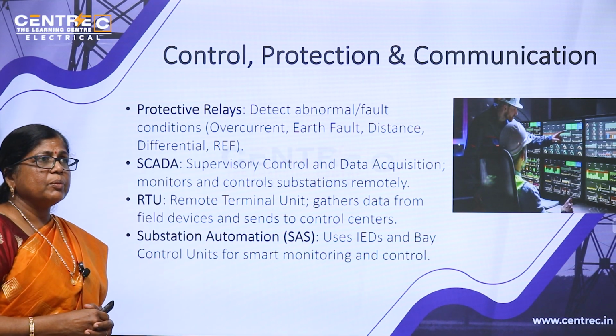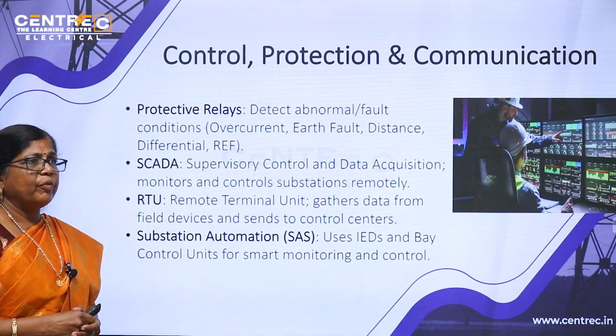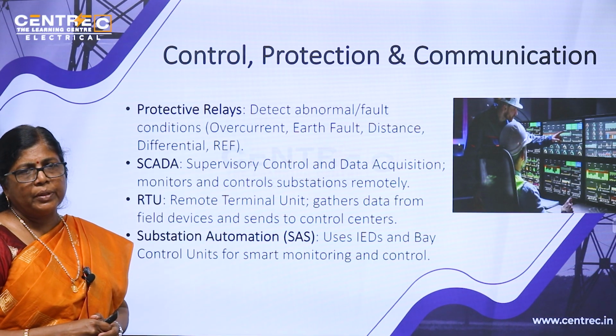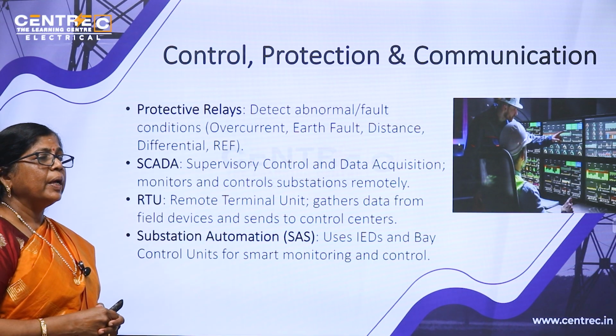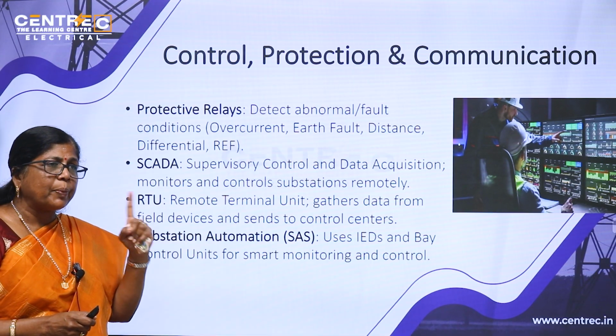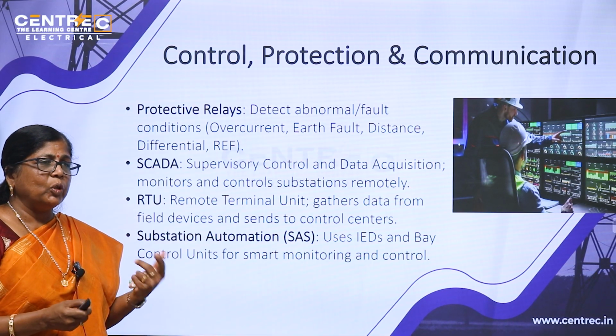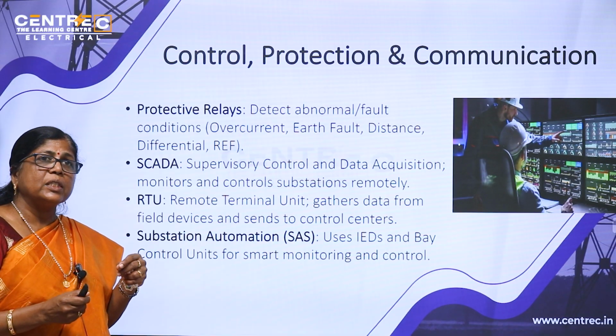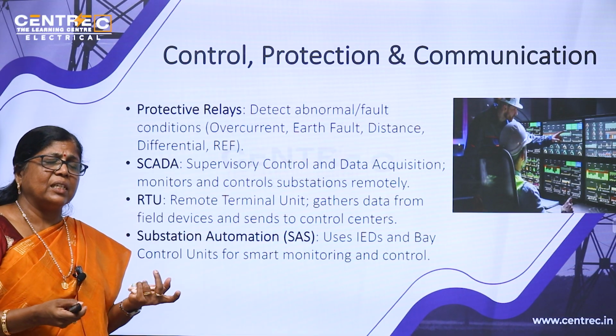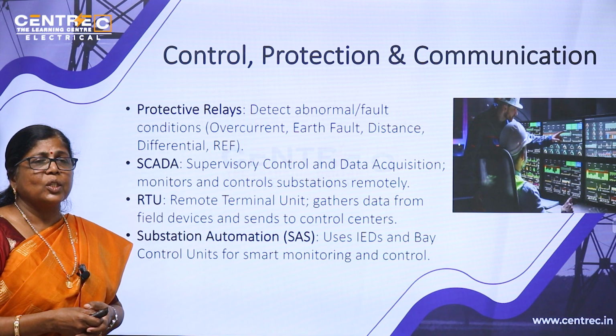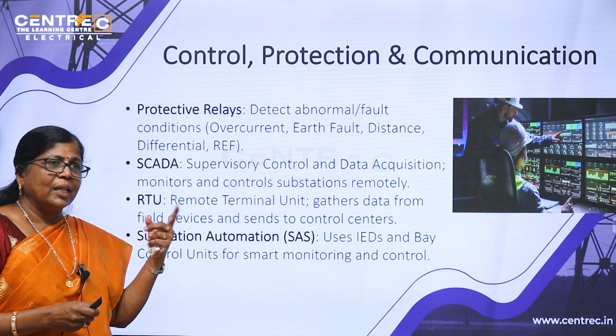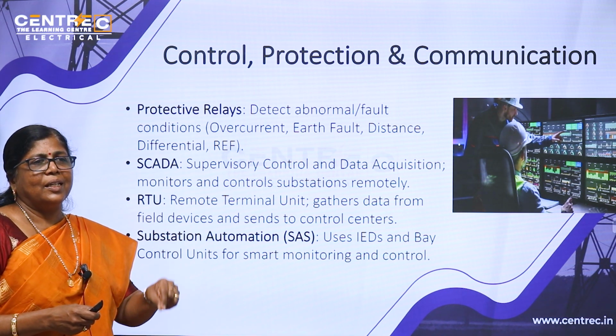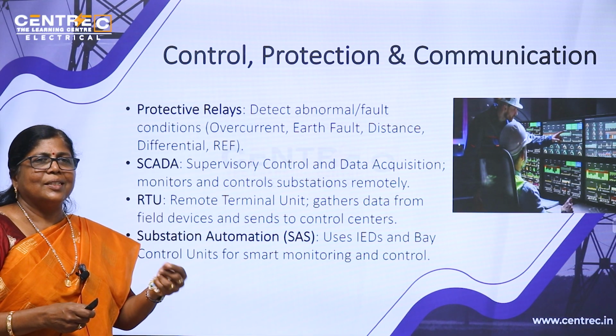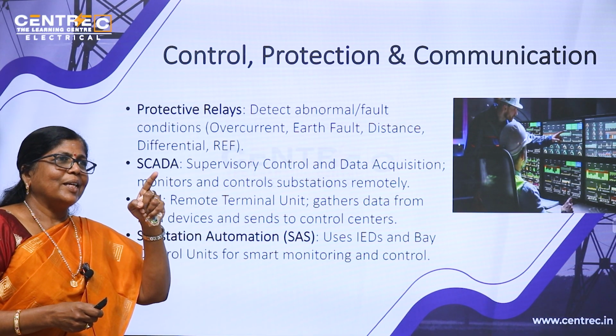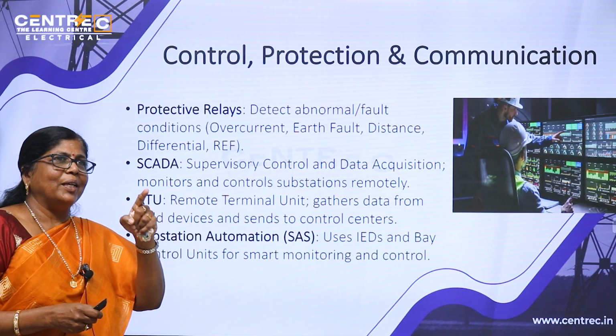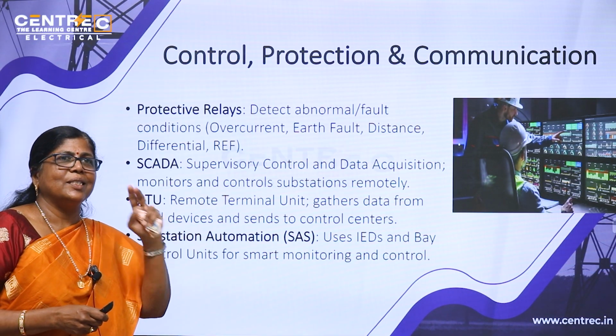SCADA system is used in Moonamattam also, because we have a load dispatch center in Kalamasheri. The operator in the load dispatch center, without any communication, can understand how much is the generation in Moonamattam or each generating station, and if it is not increased, they can call the operator in the Moonamattam power station and say that there is extra megawatt available in the third or fourth generator to increase the load.